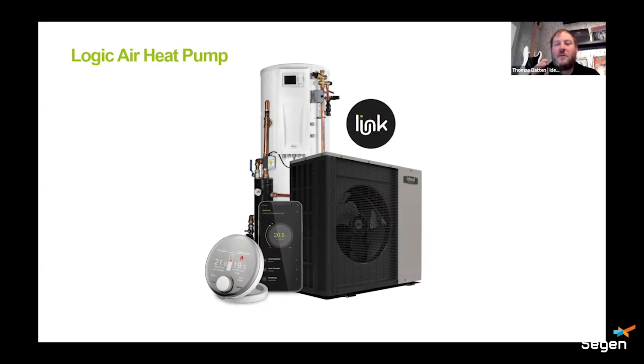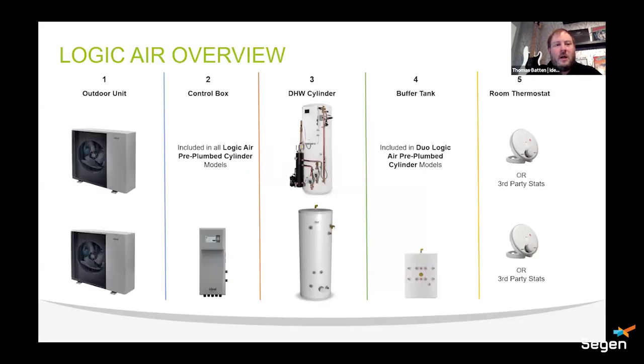So you've got the heat pump, a range of pre-plumbed cylinders designed to work with that heat pump, as well as some plain ones, and then also our own controls, which are fully compensating controls, not on-off. So there's your product overview. Choose your outdoor unit. You need some form of control box to operate that heat pump. That comes pre-installed and pre-wired on the pre-plumbed cylinders. But you can choose to use another cylinder, whether that be one of our plain ones or a third party. If you've got space problems, you need a horizontal or something like that, you can buy that control box to fit on the wall adjacent to the cylinder.